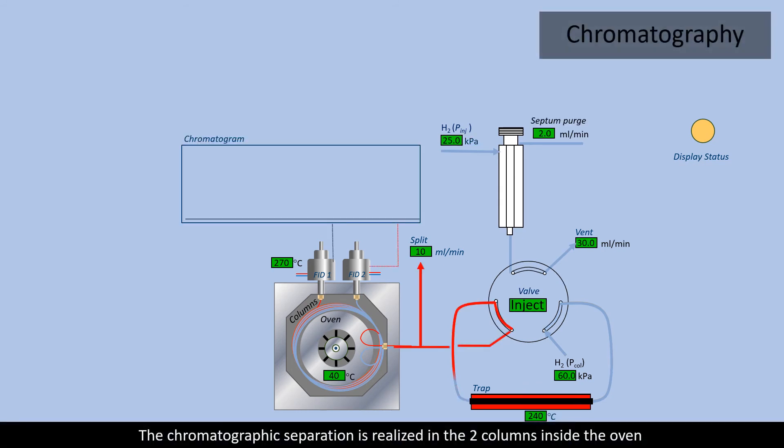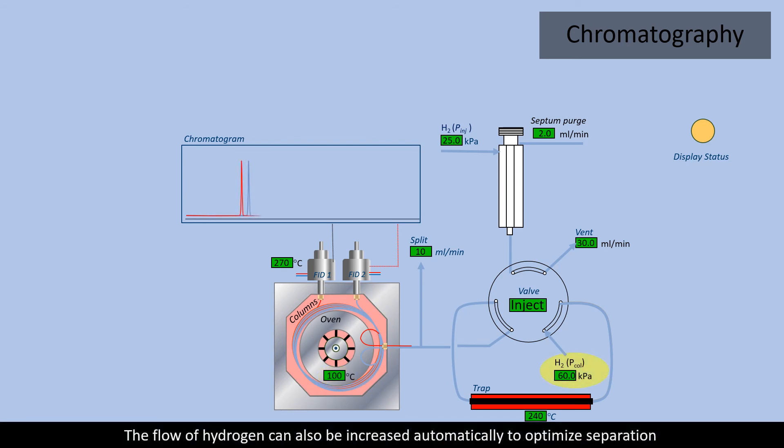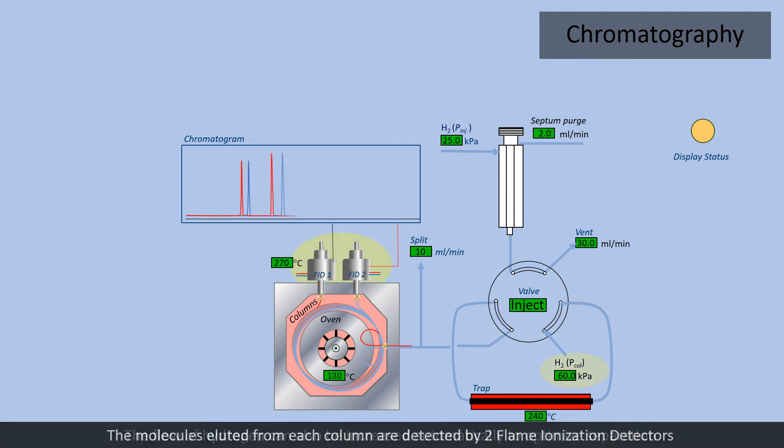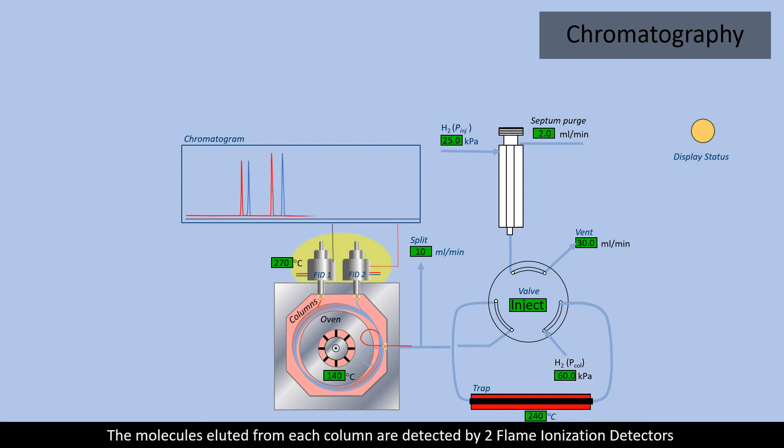The chromatographic separation is realized in the two columns inside the oven. The temperature of the oven is controlled by a precise program. The flow of hydrogen can also be increased automatically to optimize separation. The molecules eluted from each column are detected by two flame ionization detectors.